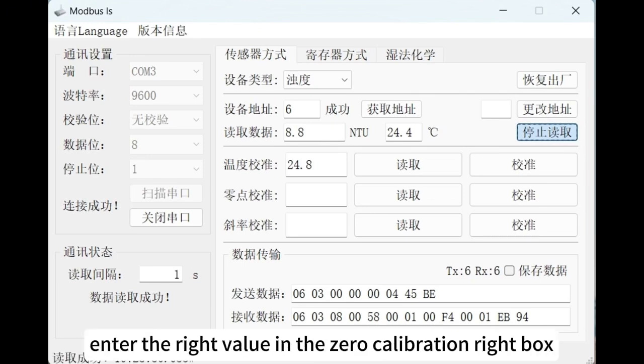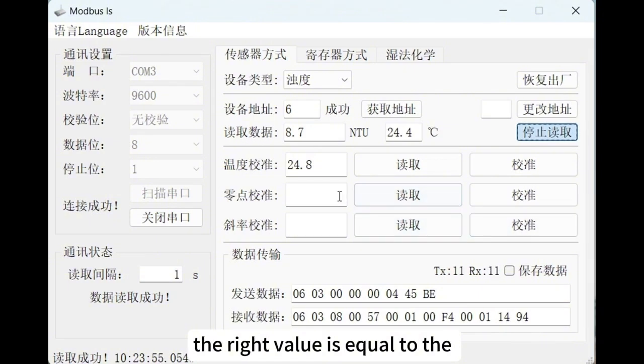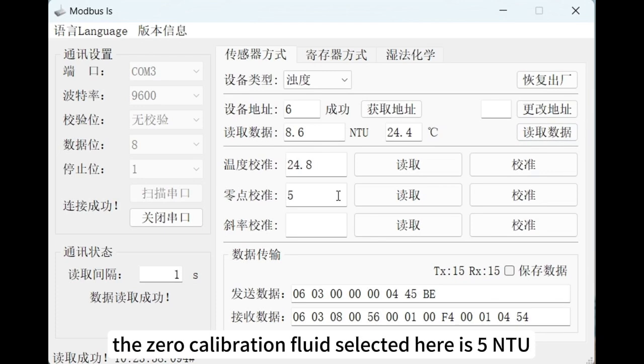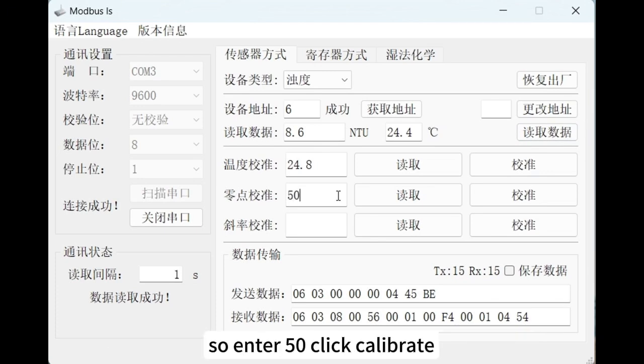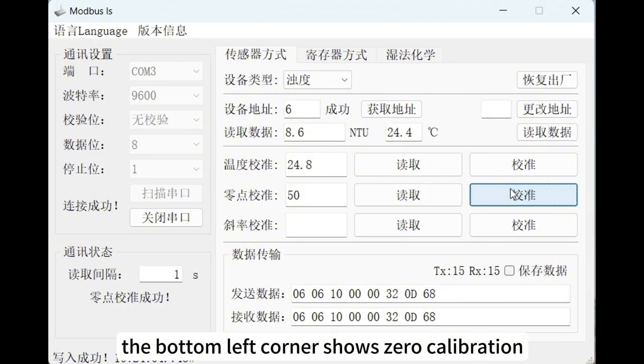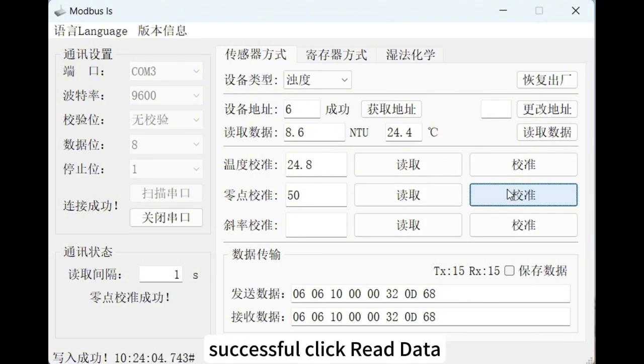Enter the right value in the zero calibration right box. The right value is equal to the actual value multiplied by 10. The zero calibration fluid selected here is 5 NTU, so enter 50. Click Calibrate. The bottom left corner shows zero calibration successful.